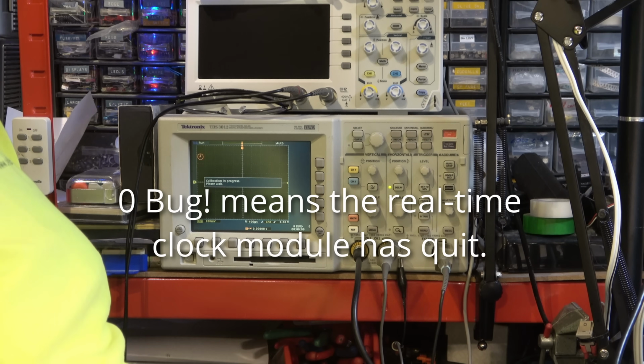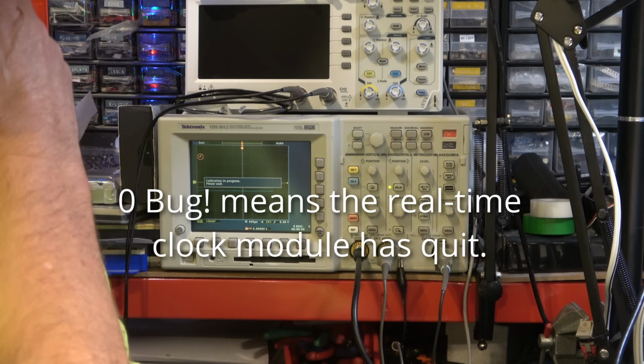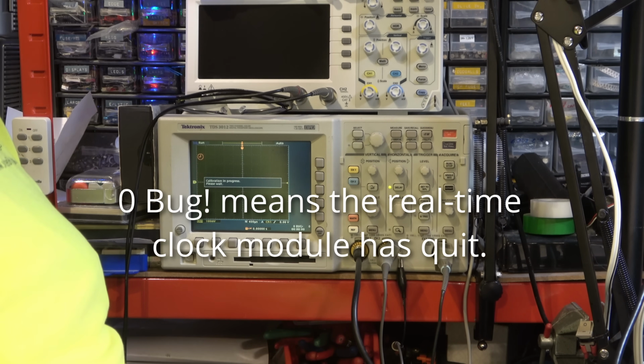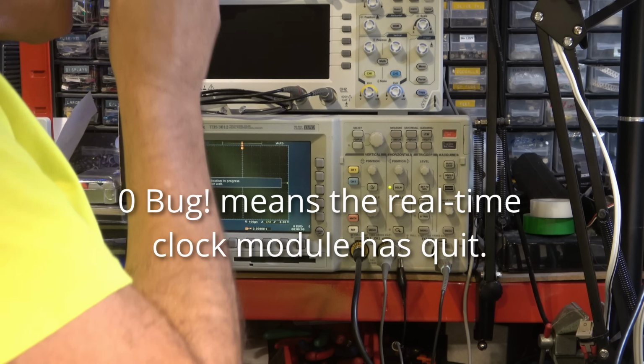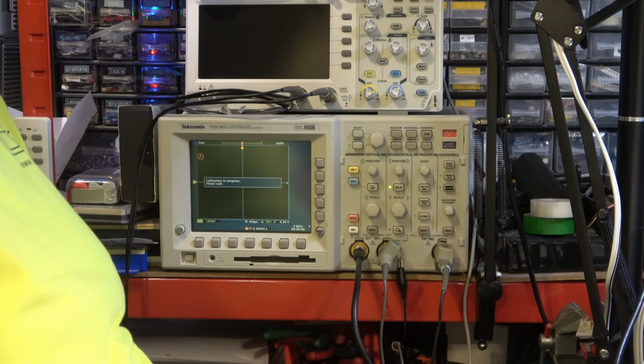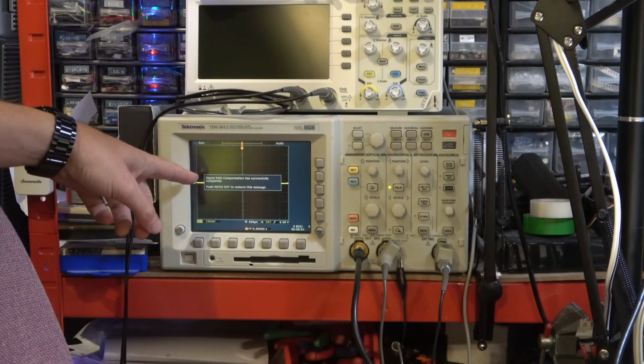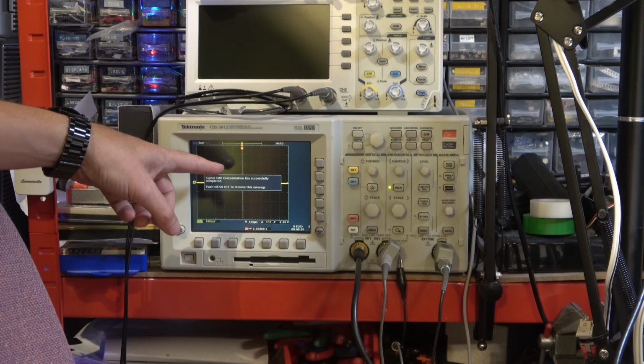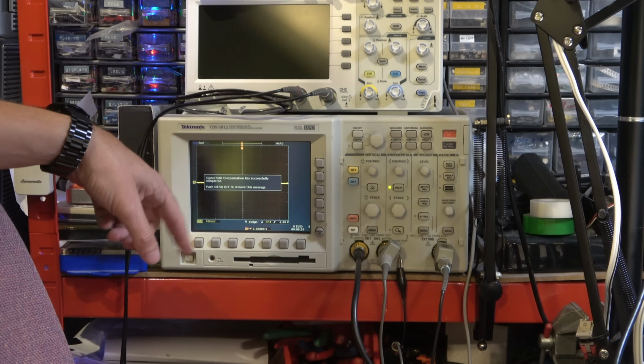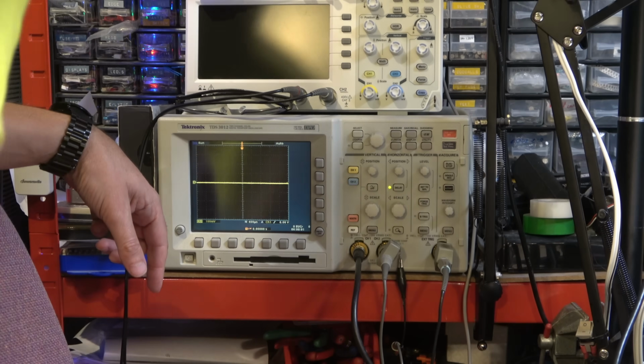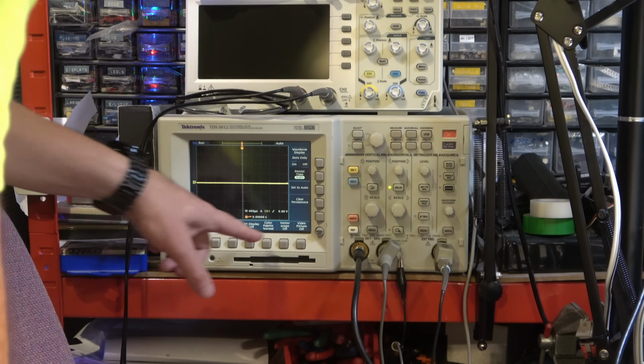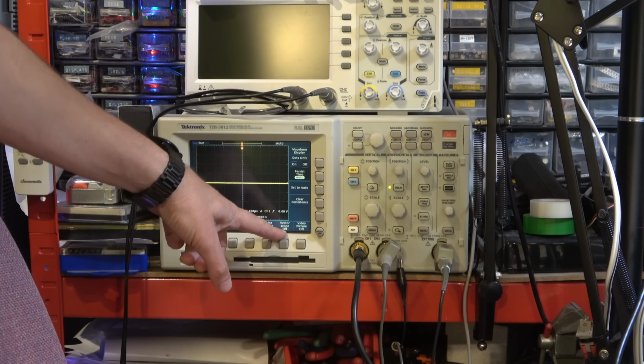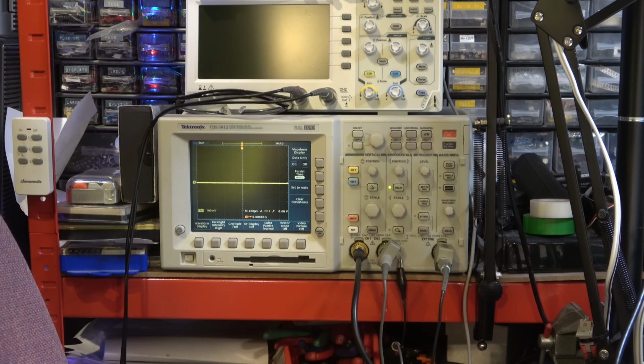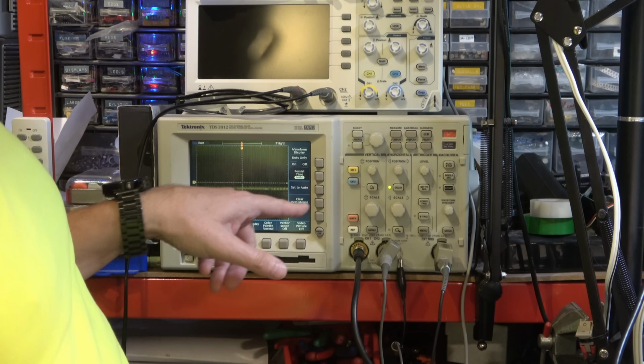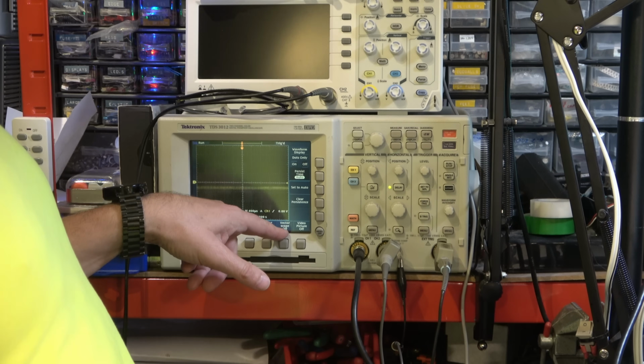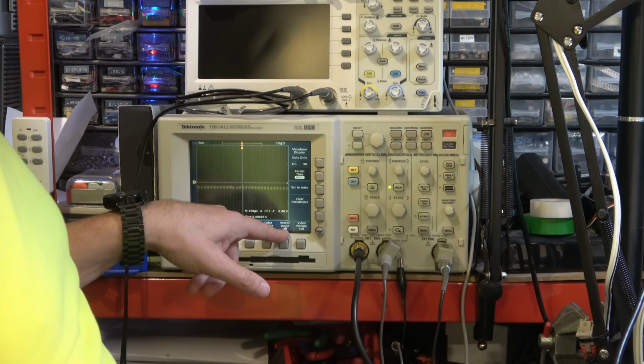I think actually maybe 0 bugs probably just means 0 bugs. I don't think so, because it had an exclamation mark after it before. Right, this is taking a while, so should we come back later? It says, signal path compensation is successfully completed. Press menu off to remove this message. Oh, good. We have vectorscope here as one of our options. Fixed it. Excellent. When we went display, we had this bit, but we didn't get vectorscope on.